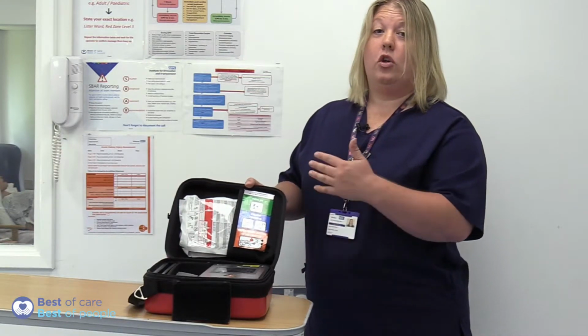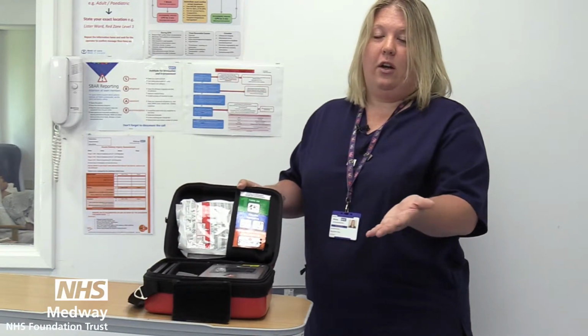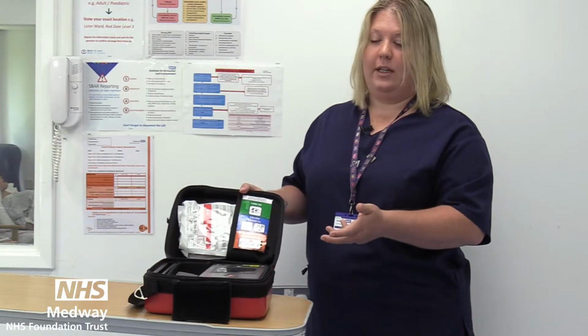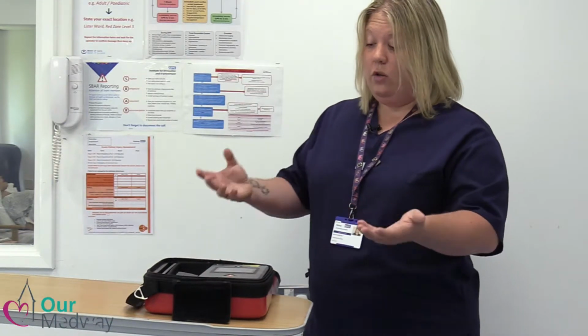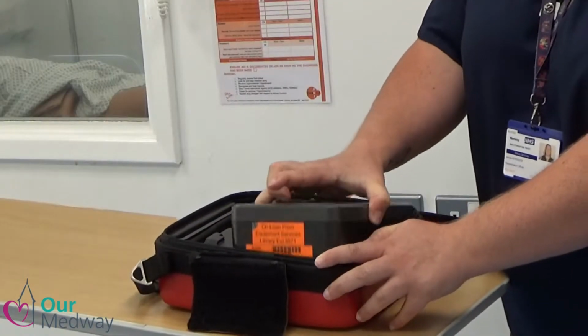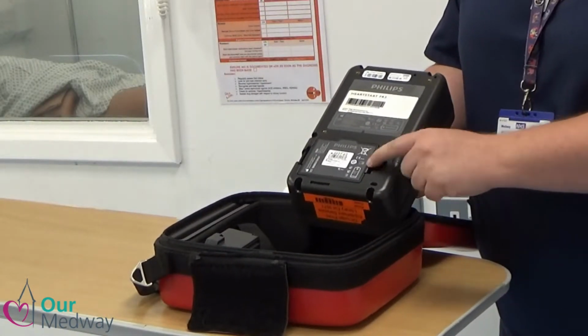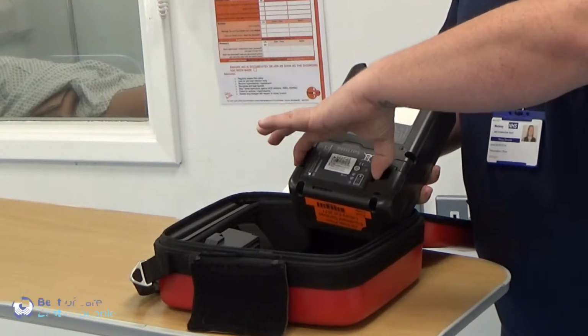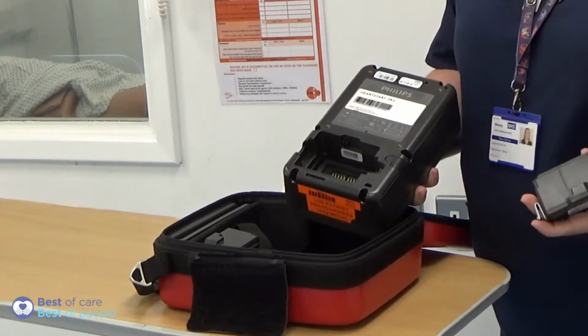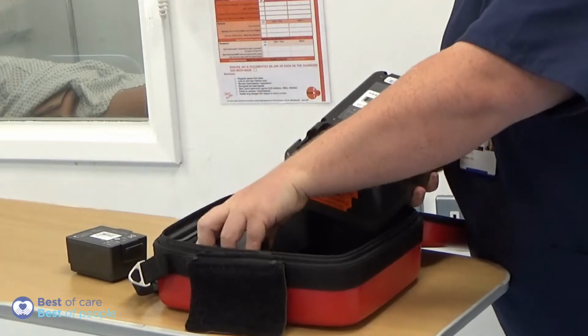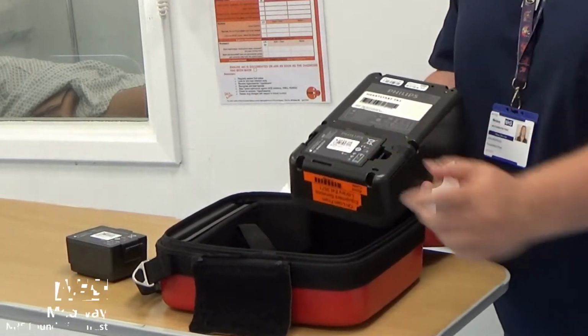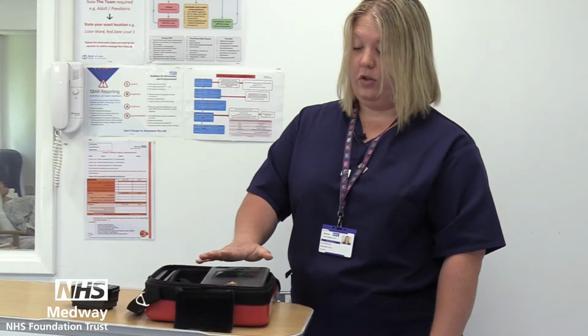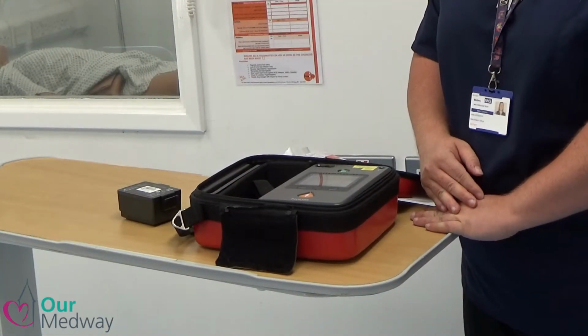Flat batteries is one of the most common things that we have to deal with. Although the batteries will last us a long time, they will eventually, like everything, come to the end of their life and we will need to change them. In order to do that, you will need to remove the defibrillator from the case, and you'll see on the back that you've got your existing battery. Pinch in the clips to remove it, and then simply clip in your new battery. If you do not have a new battery or a spare, then you need to contact the equipment services team and they can provide you with a new one.